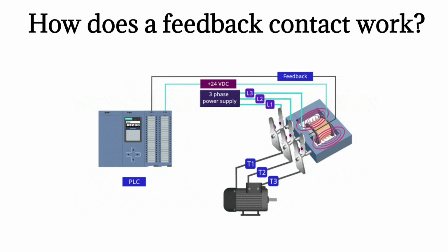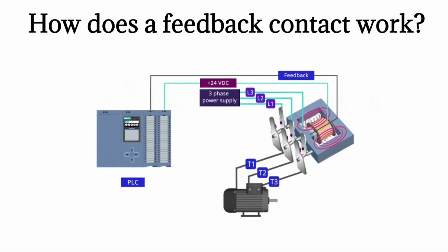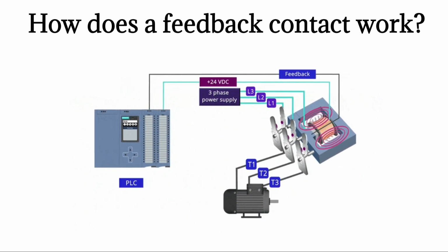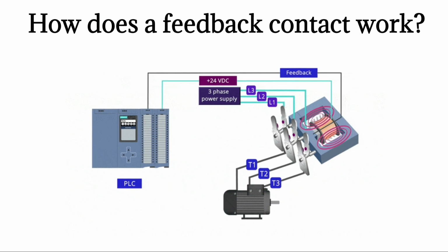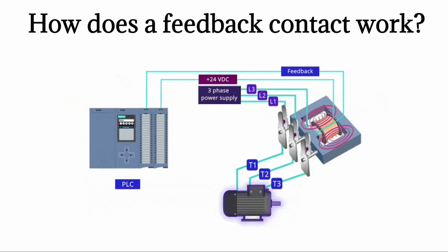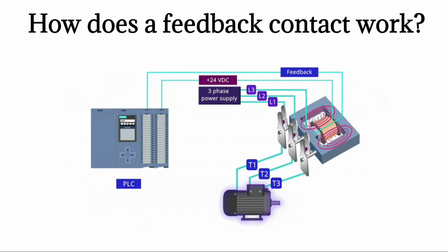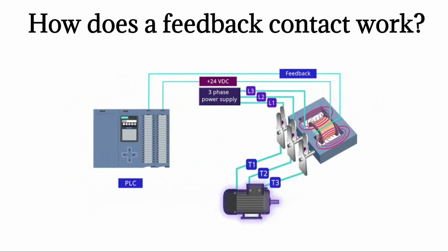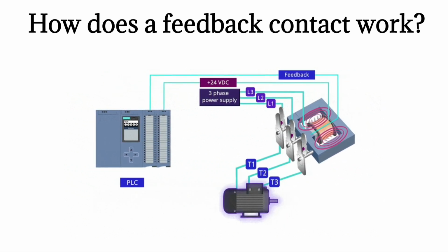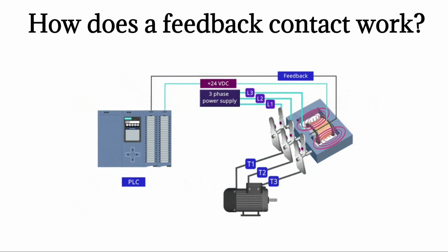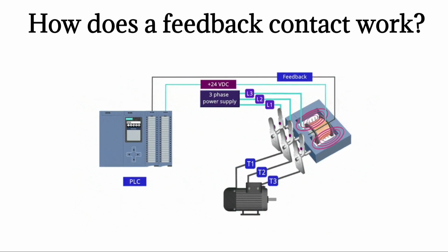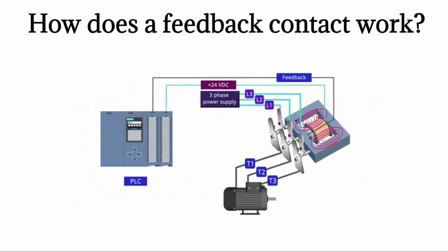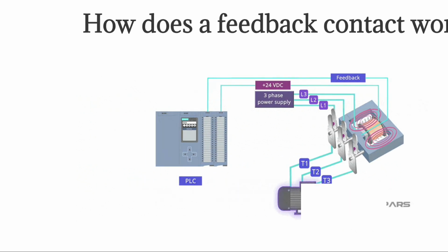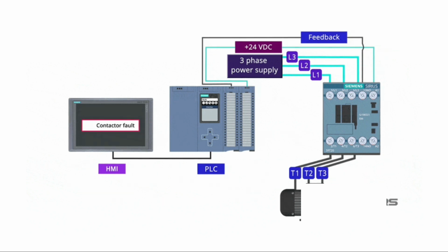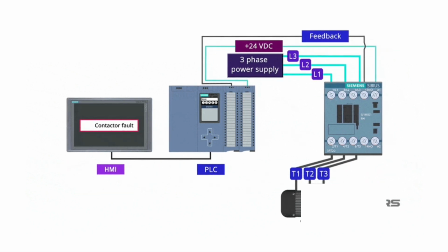The way that this contact works is that when the coil is energized and these three main contacts are closed, this feedback contact will be closed as well and send a signal to the PLC input. However, when the contactor is broken and energizing the coil will not result in these three main contacts being closed, the feedback contact will not be closed either and no signal will be sent to the PLC input. This way, there is a way for us to be notified if the contactor is broken.